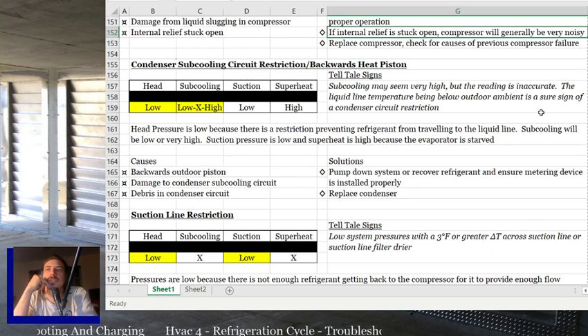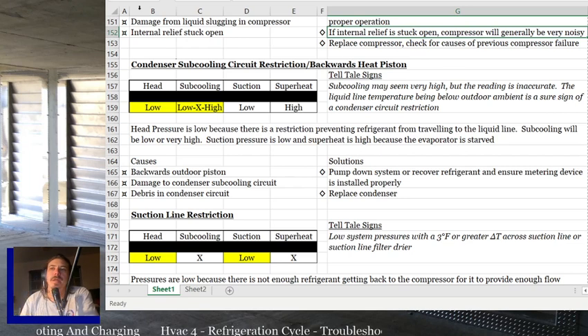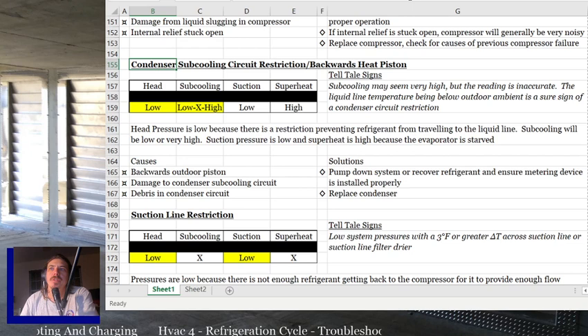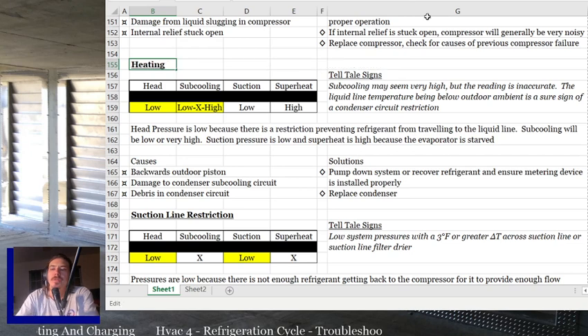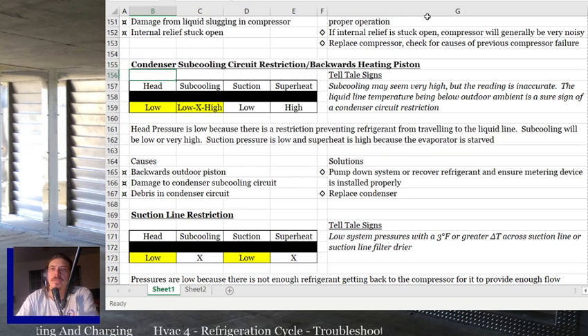Condenser subcooling circuit restriction, or a backwards heating piston. So, backwards heating metering device. I've only ever seen this once, and that's what it was, the backwards piston in heating, because it was double metering basically.